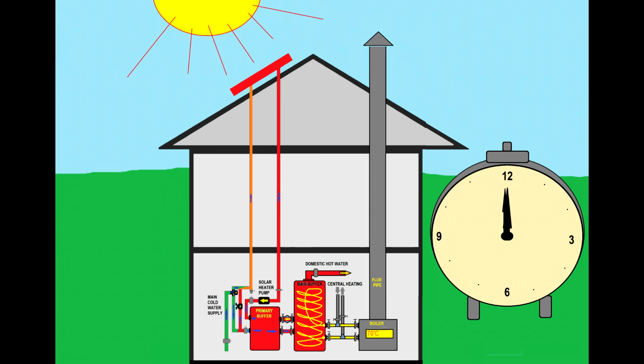This I want you to remember from time to time. That pump will circulate the water from the main buffer into this primary buffer and will heat the water, and then you will kill the Legionella, and then the pump will stop again. While this cycle happens, the ring circuit of the primary buffer will be turned off, because you do not want that high temperature of the primary buffer to migrate into the solar heater panel.